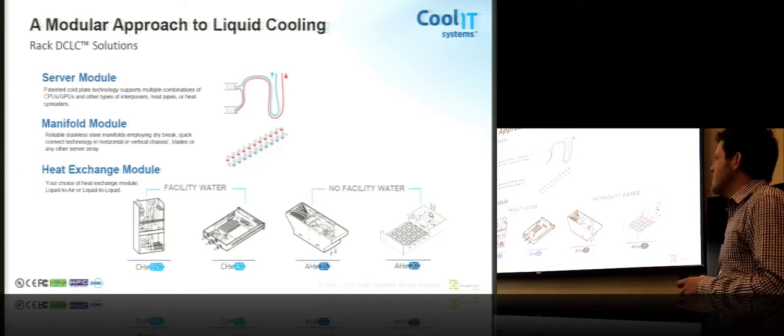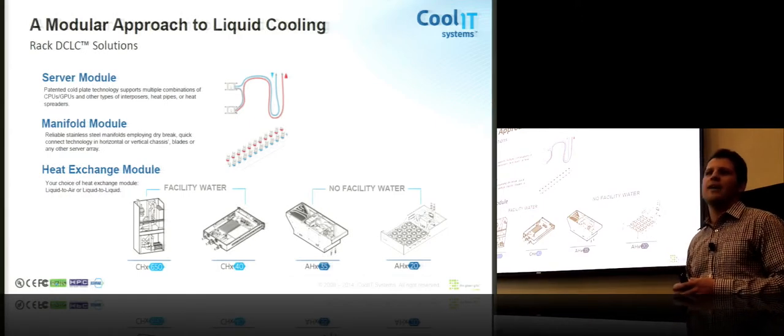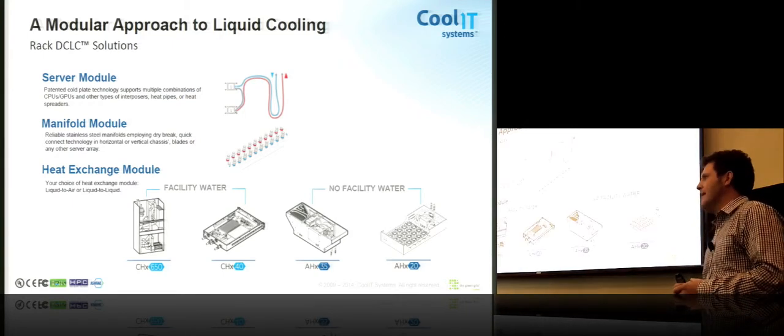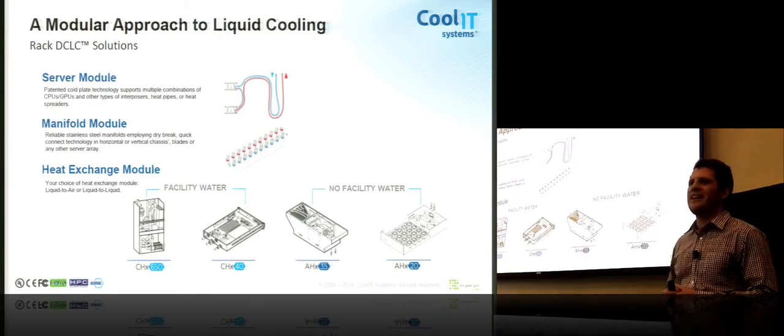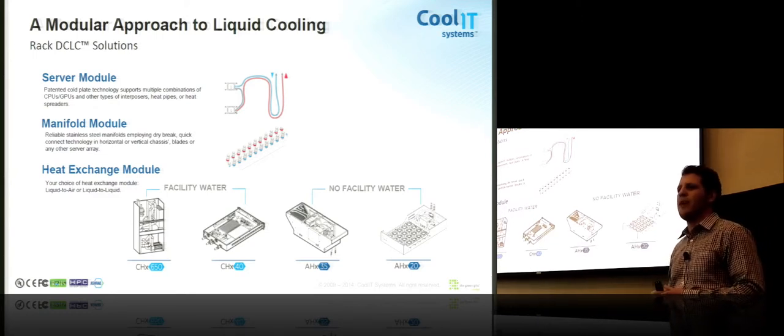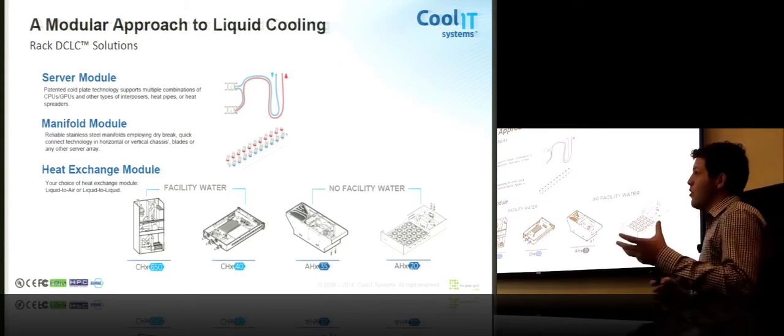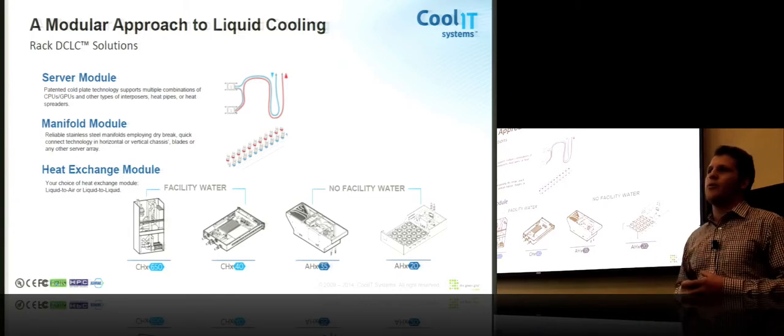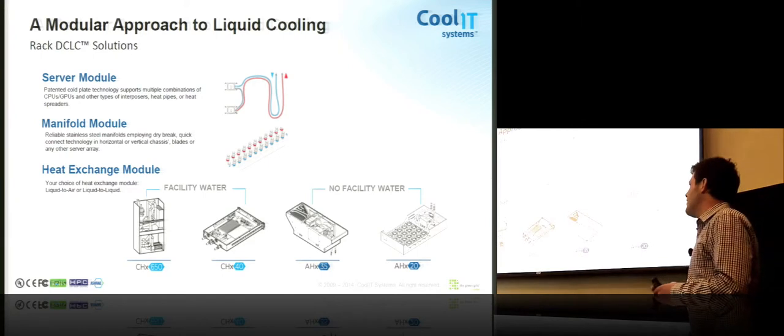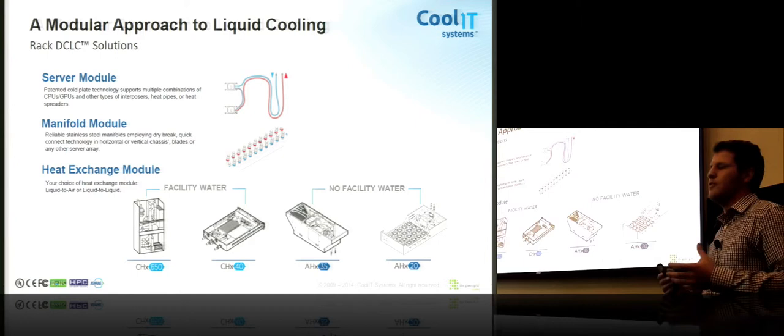Next on the module list is manifold modules. They're quite simple. It's a supply and return tube that gets racked at the back of the rack usually, just like a PDU. It is equipped with a whole bunch of quick connect sockets, and each individual server will plug into one level on this manifold. Essentially what we're doing is delivering treated cool or warm coolant to the servers. They're picking up the load of the cold plates, and they're evacuating it out the other side of the manifold.